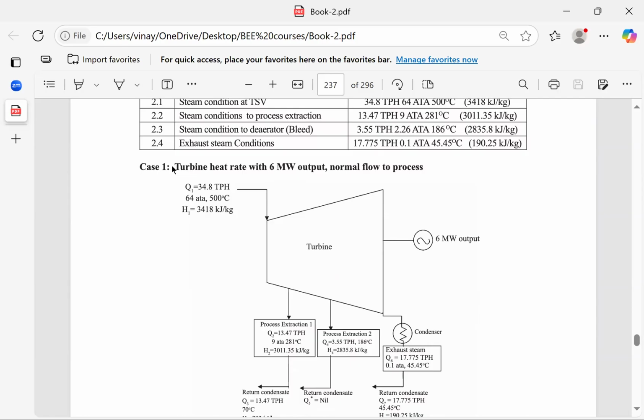Here, ready-made, he has given you the quantity of steam as 34.8 tons. When solving this example, you will have to convert these tons into kgs because all other parameters of heat etc. are per kg. So it becomes 34,800 kg. The pressure is 64 kg per centimeter square, and the temperature is 500 degrees centigrade. At these parameters, the heat content per kg of steam is given. Here the example uses kJ, but normally in the exam they will give you kilocalories. If you want to convert these, go to the joules and kilocalorie conversion factors which are given.